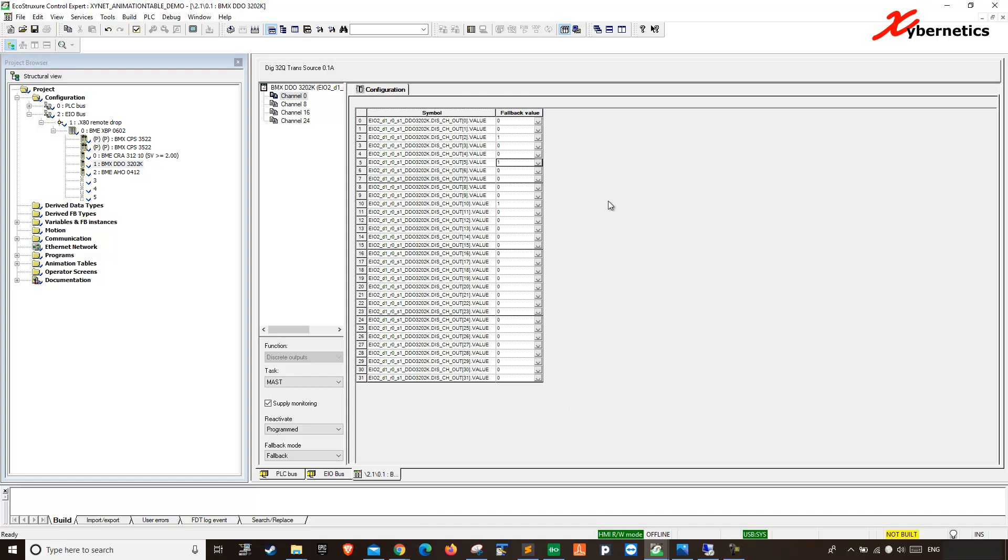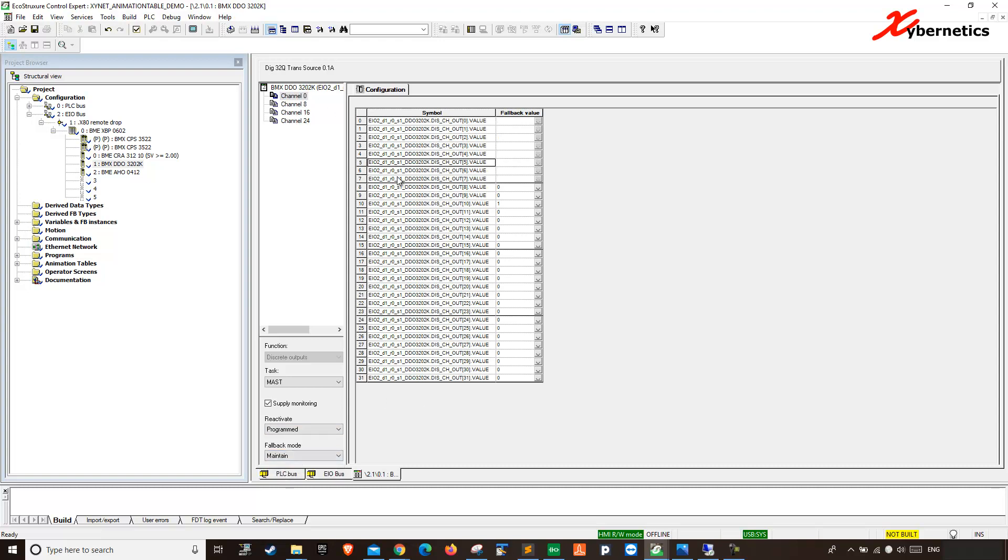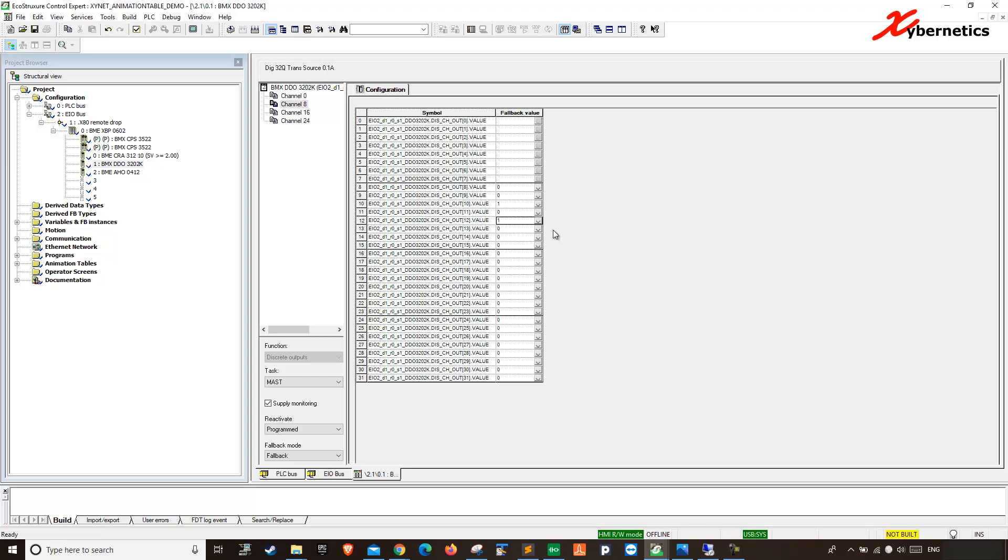But in an event that, let's say, if you want the PLC program to maintain its old settings, whatever it was before the power went down and it comes back on again, what you do is that you go your fallback mode, you change it from fallback mode to maintain. That's what channel 0 to 8. And you can still characterize the rest of the channel as custom. Like that.